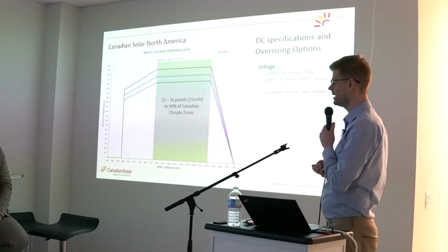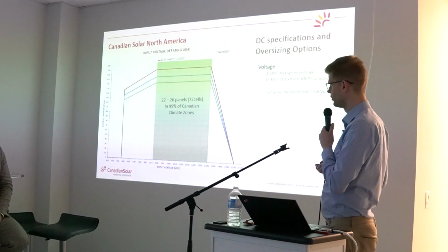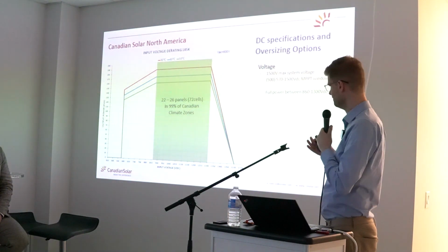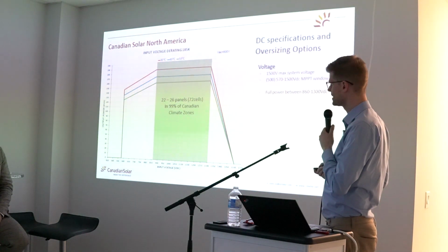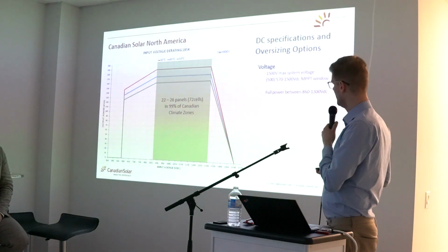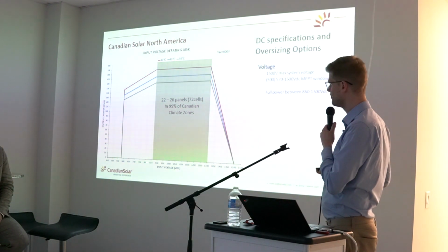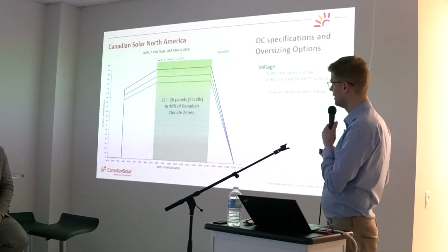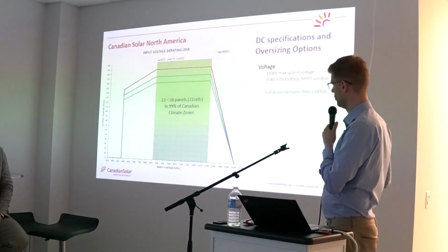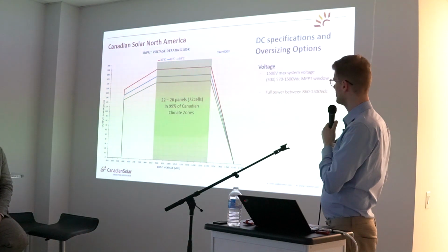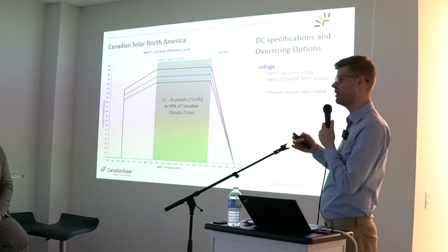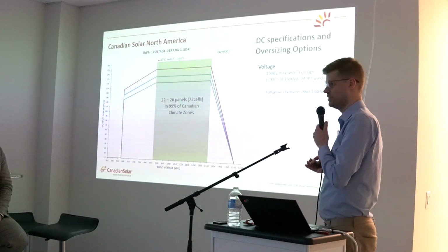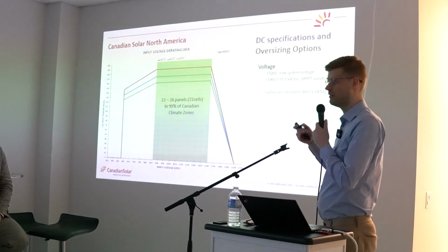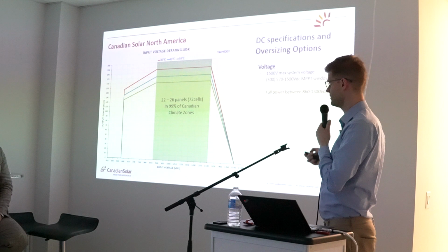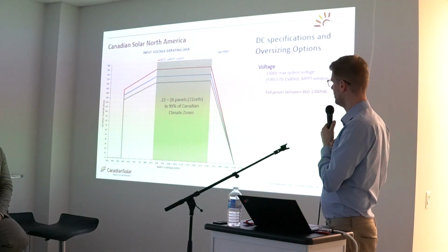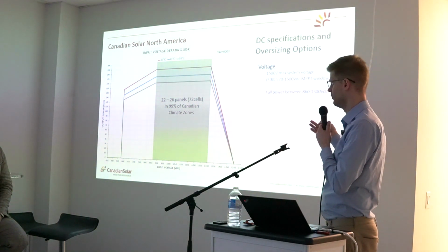Which means in a Canadian climate, you have a very wide input voltage range available to you and your string design. And with that system, we typically operate somewhere in the range of 860 for full power. You see here the full power of the units, all the way up to about 1,300 volts. And the entire range is actually quite wide. So even if you have, let's say, partial shading conditions or some of the panels are covered in snow, you can still use the remaining panels that are not covered all the way down to about 500 volts as long as the inverter is already in operation.